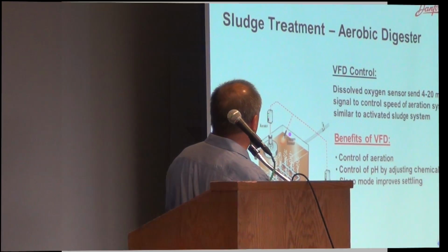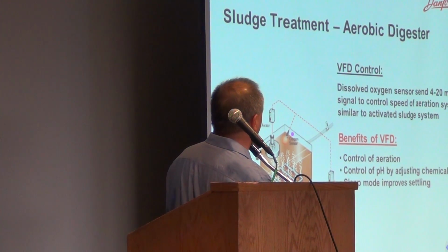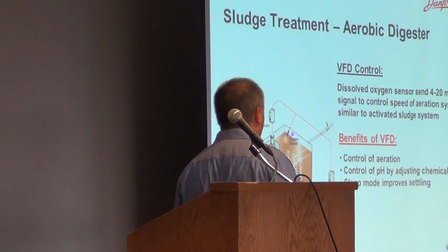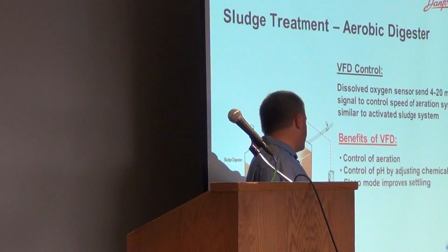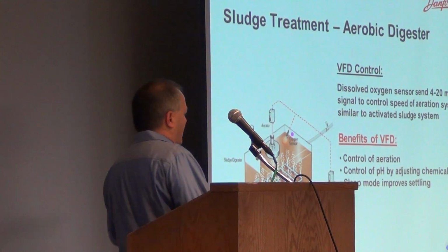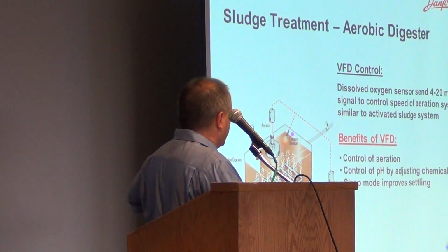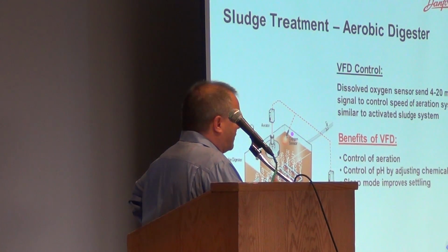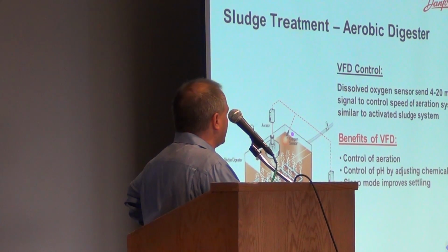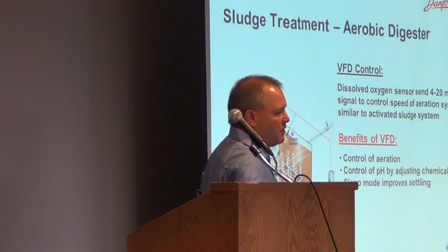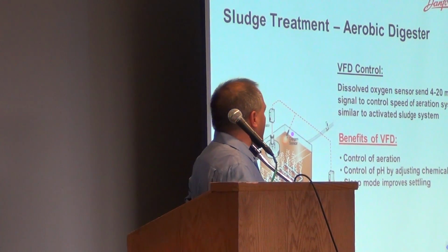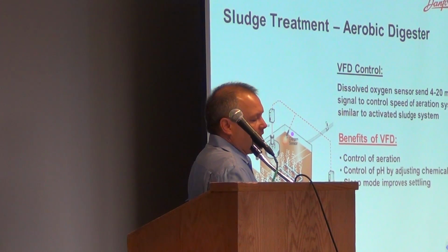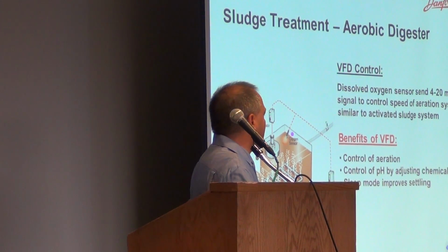Digester, once again, controlling the aeration to control the pH and the oxygen in the system. One sensor, two drives. One on the blower, one on the mixer. Or you might not have the aerator on top. You might have the blower system. We can control the drive with an oxygen sensor, or the oxygen sensor can go back to your SCADA or whatever you're currently using to feed the drive a signal to maintain whatever you're looking for.